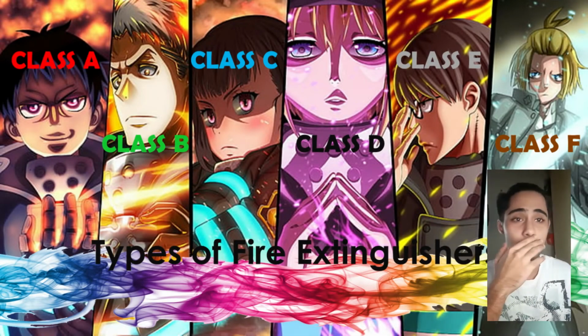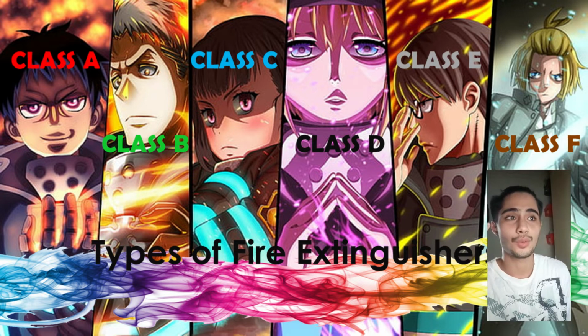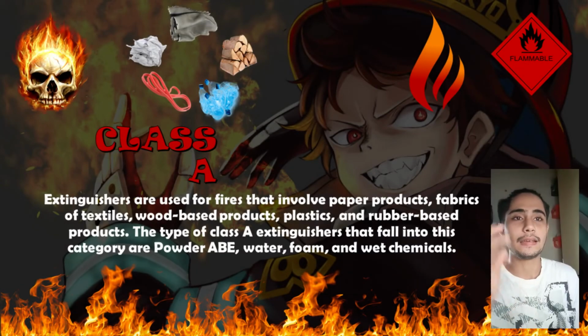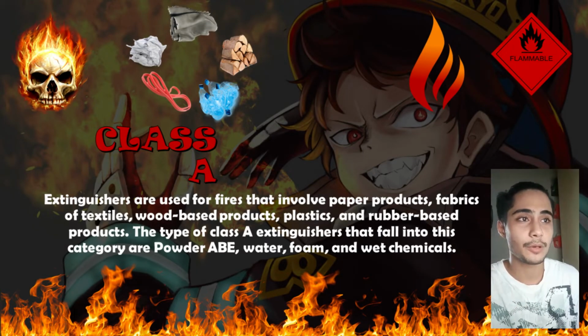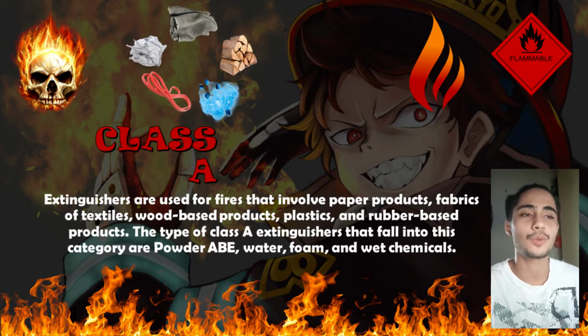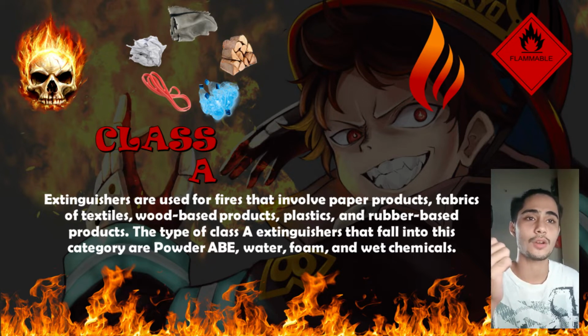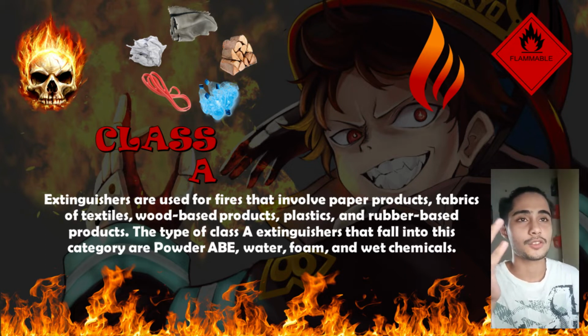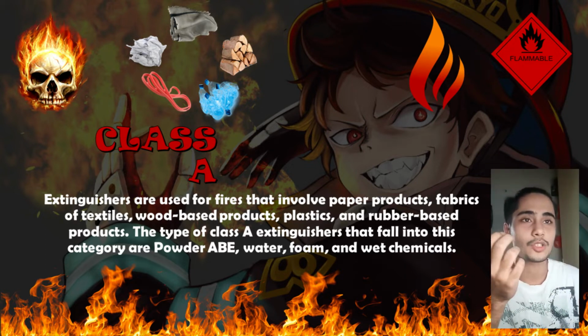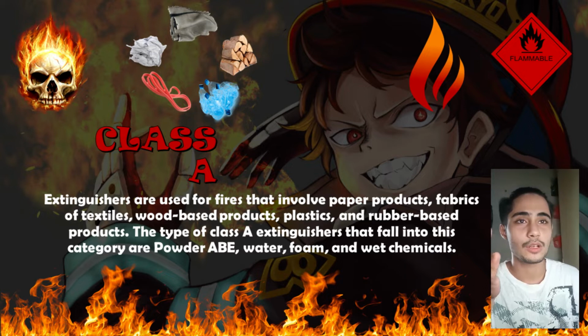So we are now at the types of extinguisher from class A to class F: A, B, C, D, E, F. Class A extinguishers are used for fires that involve paper products, fabric or textile, wood-based products, plastic, and rubber-based products. The types of extinguisher that fall into this category are powder ABE, water, foam, and wet chemicals. Here above you can see examples in the pictures: plastic products, rubber-based products, paper, fabric or textile, and wood-based products.